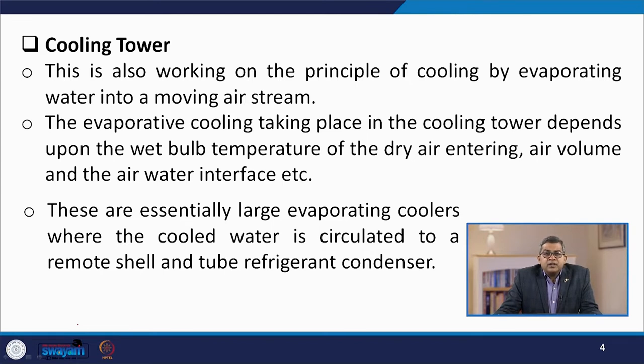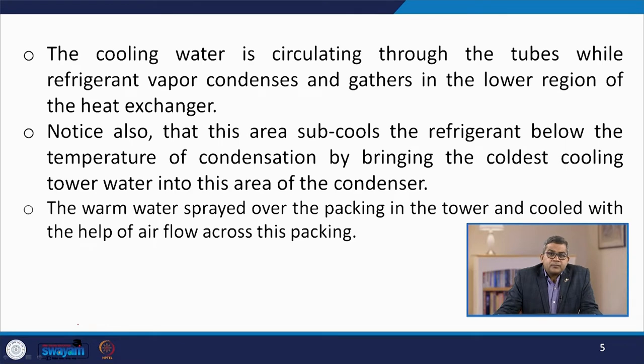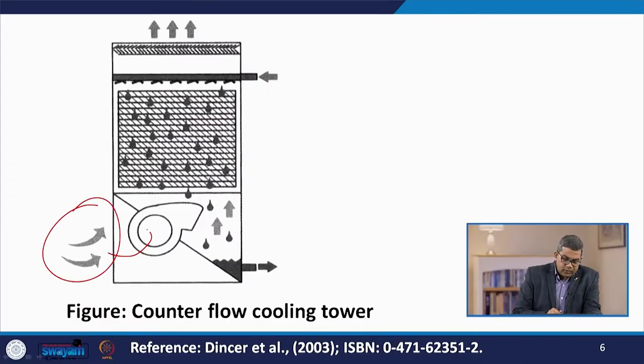These are essentially large evaporating coolers where the cooled water is circulated to a remote shell and tube refrigerant condenser. The cooling water is circulated through the tubes while refrigerant vapor condenses and gathers in the lower region of the heat exchanger. This area subcools the refrigerant below the condensation temperature by bringing the coldest cooling tower water into this area of the condenser. The warm water is sprayed over the packing in the tower and cooled with the help of airflow across the packing, where air circulates through the mesh packing and the water droplets exchange heat.